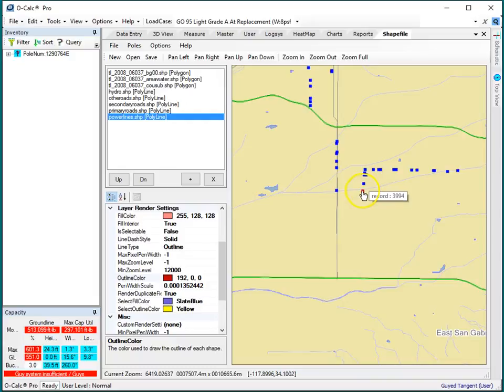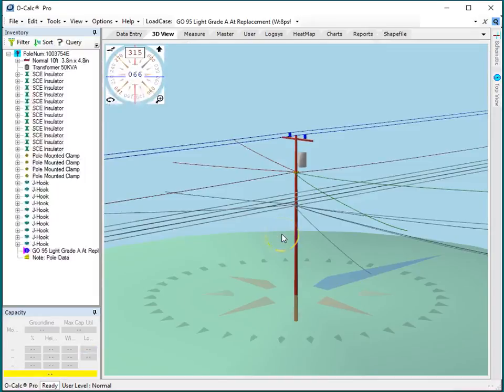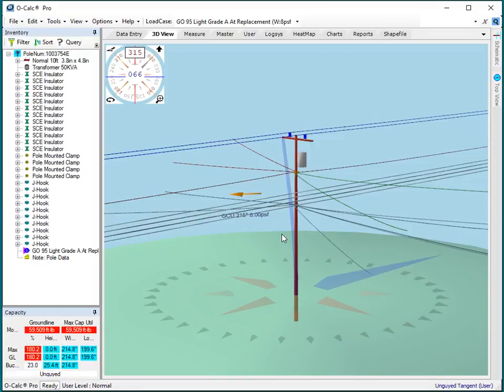So if I pick on one, what it does is goes ahead and loads that pole up and recalculates for me, and as expected it is in fact overloaded. And so what I get is sort of a mini GIS system.